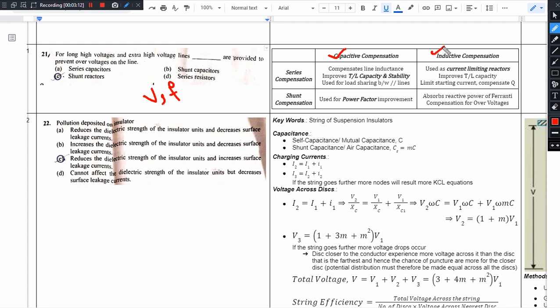In this compensation, we have capacitive compensation and inductive compensation. These capacitors and inductors we can place in series or we can place in shunt or parallel. In some cases we place them in series, in some cases we place them in parallel. First, capacitors. When do we place capacitors in series? To improve transmission line stability and transmission line capacity, we place capacitors in series for stability.